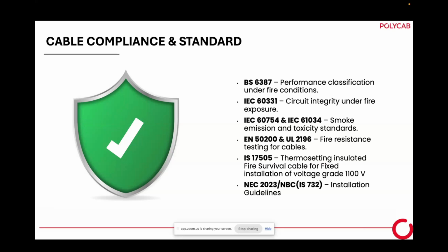IS 17505 has recently been released by the Bureau of Indian Standards, and they have made it mandatory. Whoever is manufacturing fire survival cable has to take approval under IS 17505, and then you can sell it in the market. Any cable supplier from outside the country, if they want to sell their fire survival cable in India, has to take IS 17505. Otherwise, there will be legal action from the BIS. NEC 2023 and NBC IS 732 installation guidelines. I'll tell you, there is a very good, nicely drafted NEC 2023 and NBC IS 732 standard.